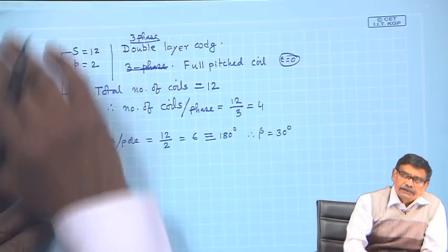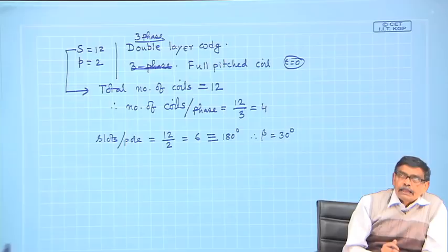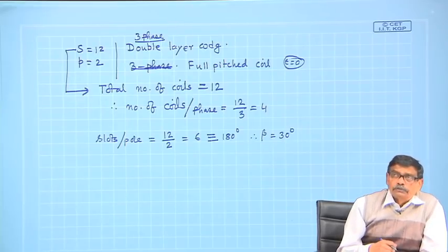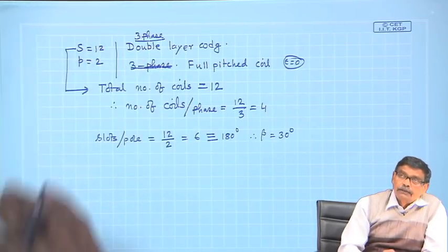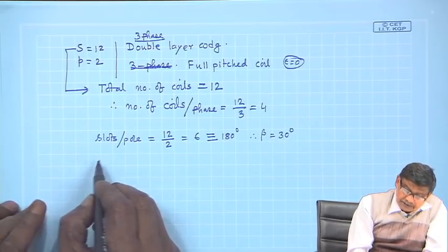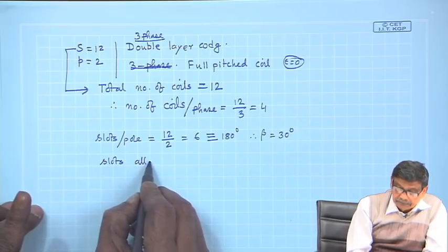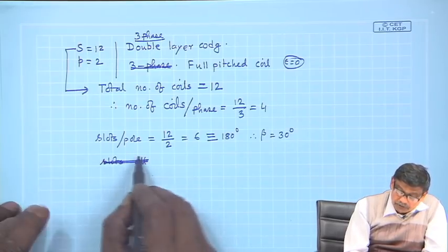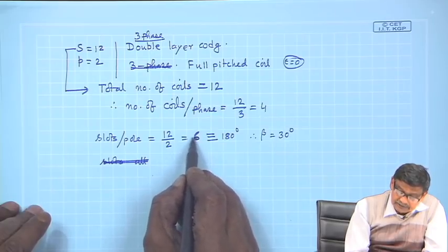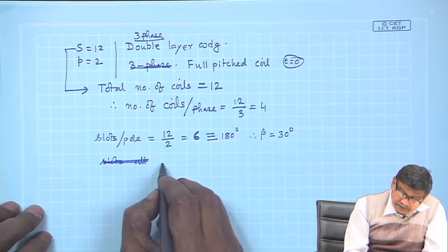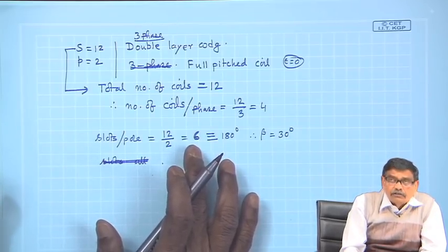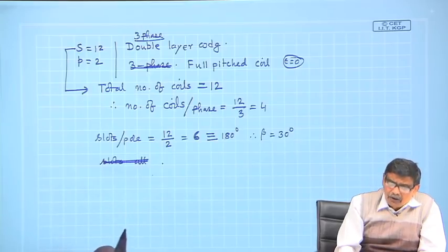First, let me do it like this without much explanation; we will explain it later, but you see how easy it is. So, there are 2 poles, total number of slots are 12.